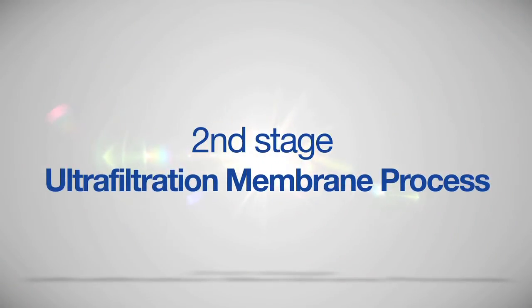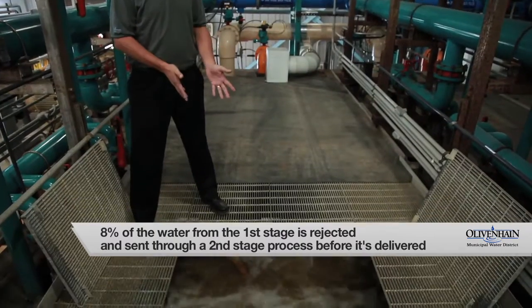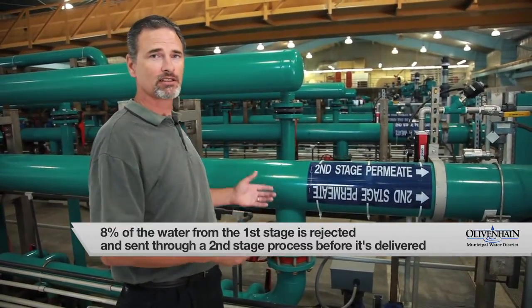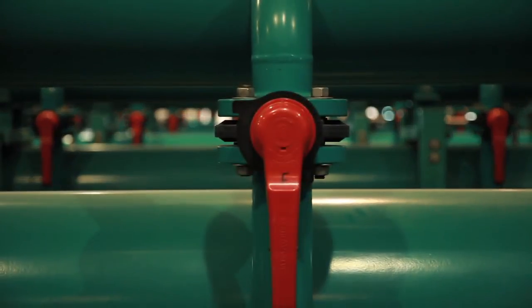Of the raw water that comes into the plant, 92% leaves the first stage as finished water. The remaining 8% that is rejected by the first stage is delivered to the second stage ultra-filtration membrane process, where suspended particles and contaminants are removed by the same membranes as the first stage.